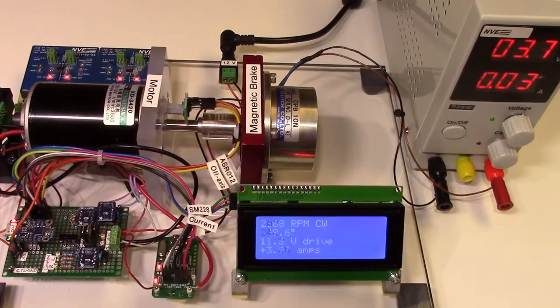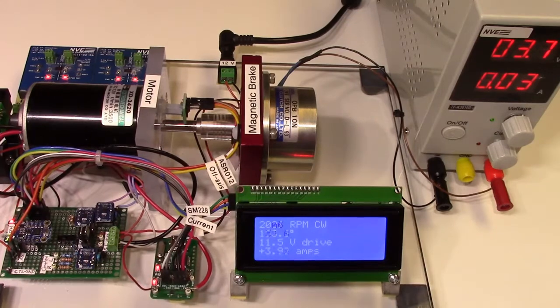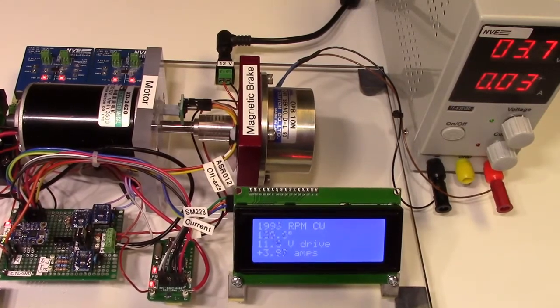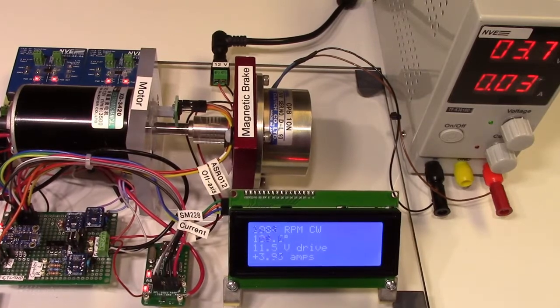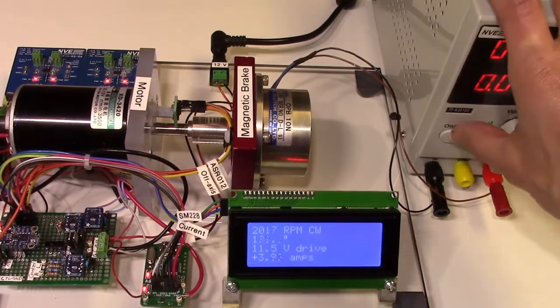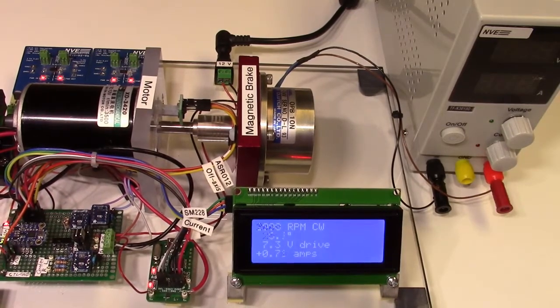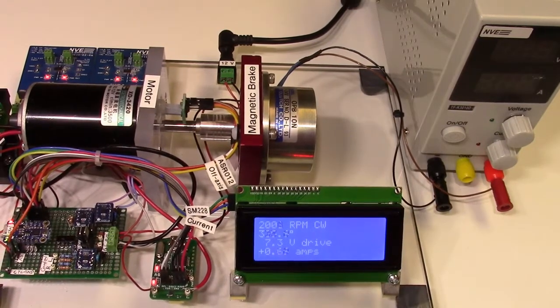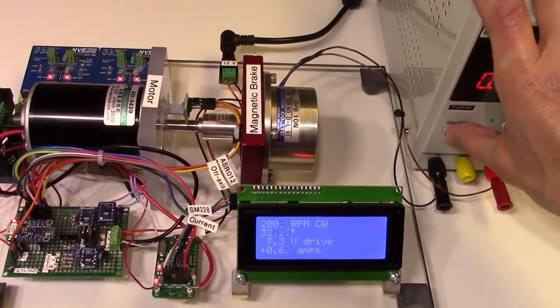This switch turns on closed loop proportional integral speed control, which adjusts the motor voltage to keep the speed close to the 200 RPM set point as mechanical loading decreases and increases.